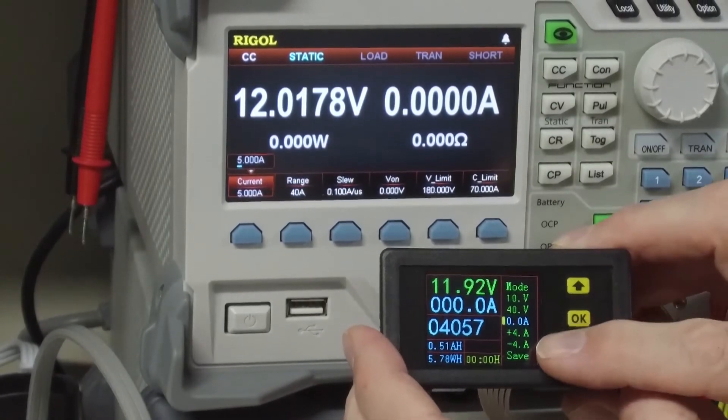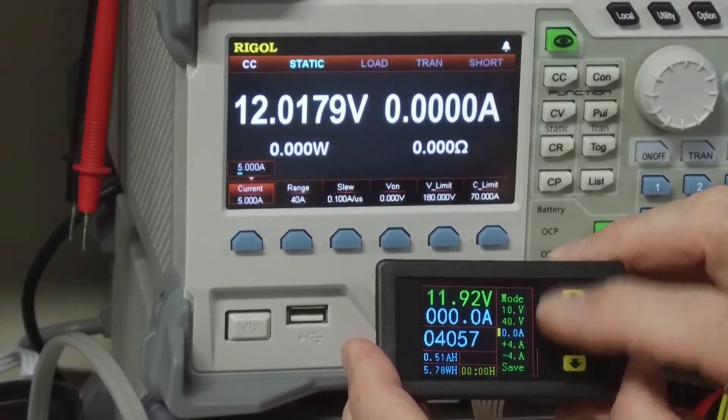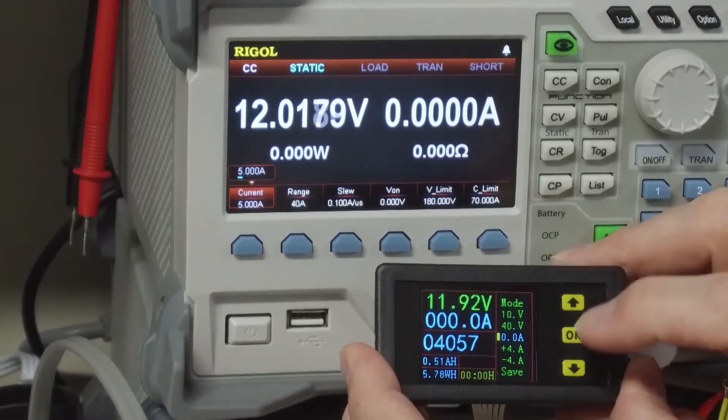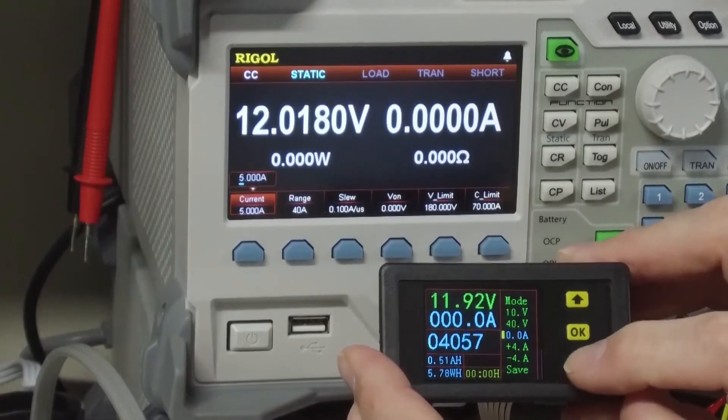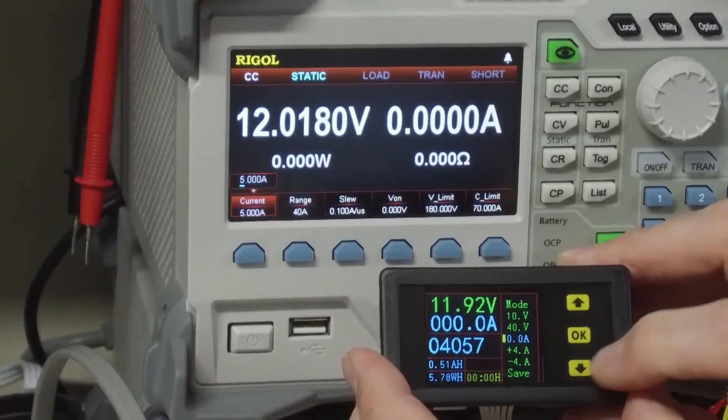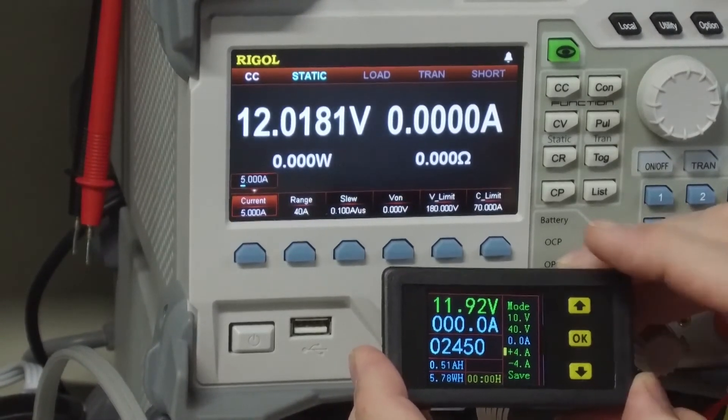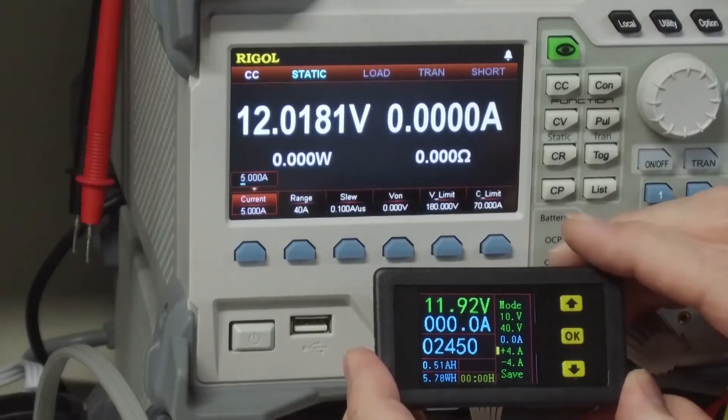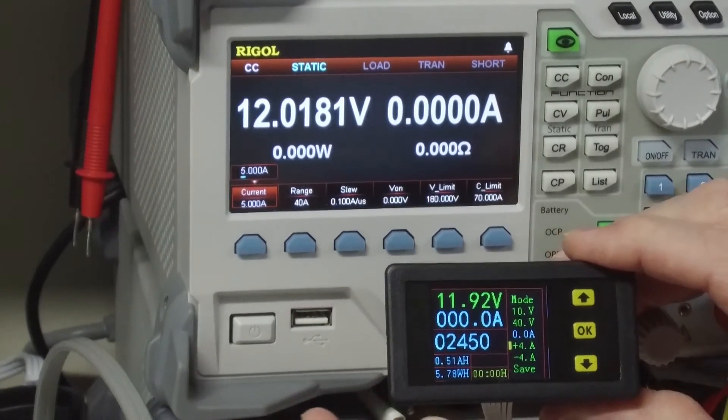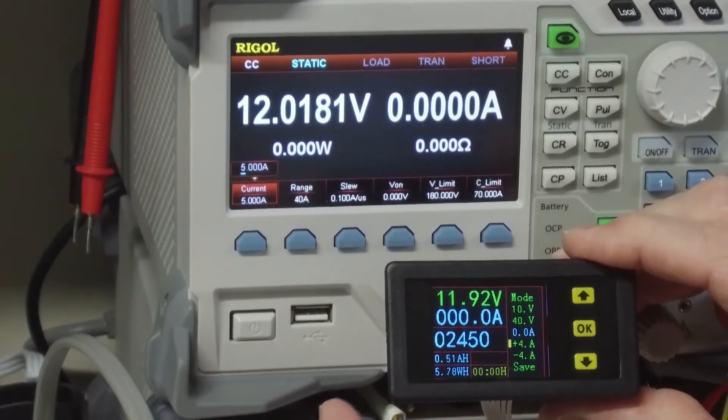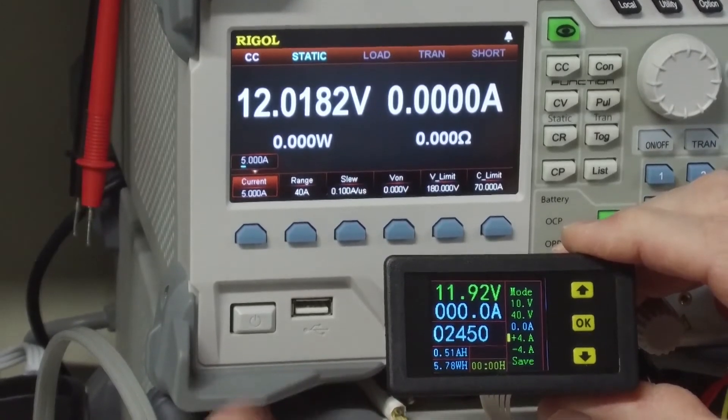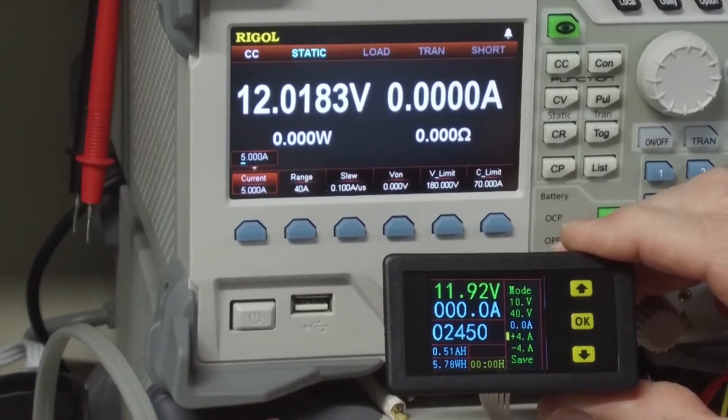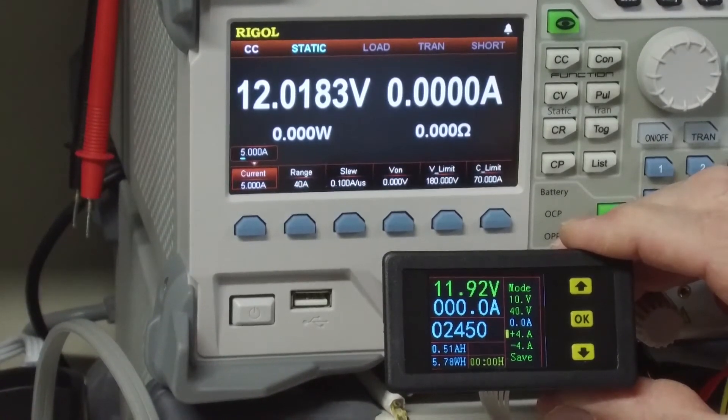I think what a lot of people are having problems with is this plus 4 amp and minus 4 amp. What you want to do is you want to calibrate, I think, typically at a pretty high current and not at, say, 1 amp or half an amp.